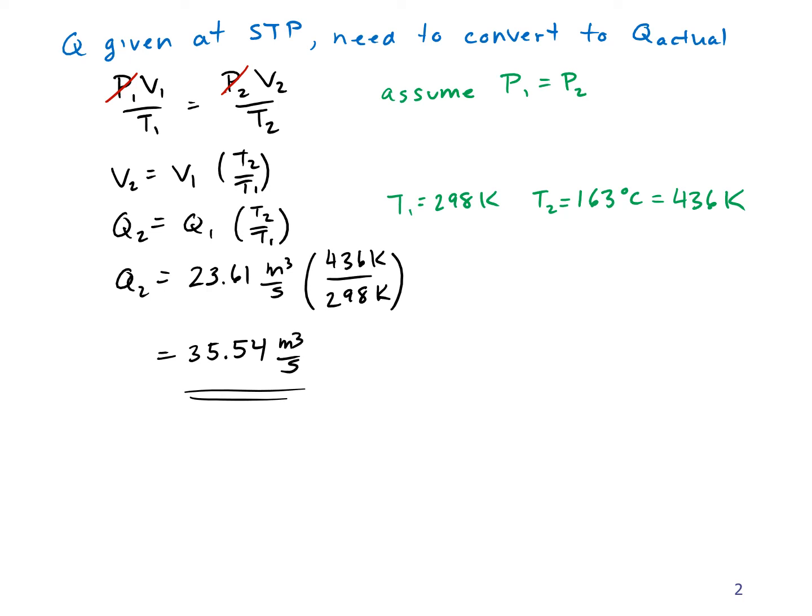That's the flow rate I will be using in the Deutsch-Anderson equation. So next up, we apply the Deutsch-Anderson equation. This tells us the collection efficiency of an ESP. It assumes mixed flow in the ESP. Eta equals the exponential of some things. I can say that A equals minus Q over W times the natural log of 1 minus eta.